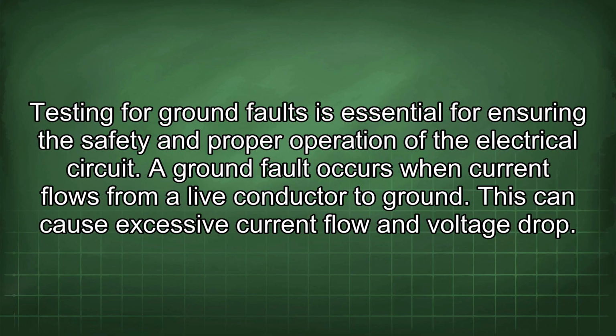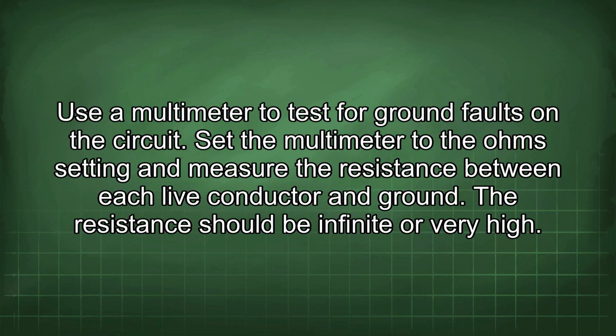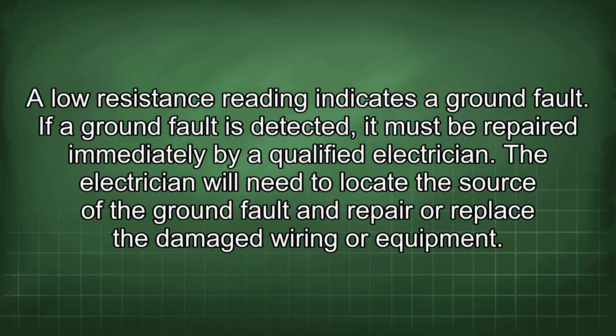Testing for ground faults is essential for ensuring the safety and proper operation of the electrical circuit. A ground fault occurs when current flows from a live conductor to ground. This can cause excessive current flow and voltage drop. Use a multimeter to test for ground faults on the circuit. Set the multimeter to the ohm setting and measure the resistance between each live conductor and ground. The resistance should be infinite or very high. A low resistance reading indicates a ground fault.